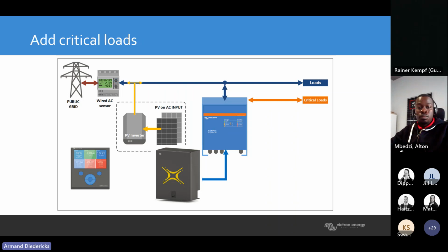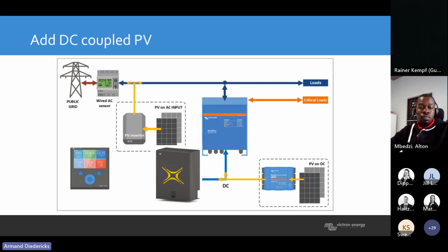and the PV inverter will switch off. If you want to add on additional PV modules on an AC coupled system, then you can add on MPPT. The MPPT's primary function is to charge the battery at first priority, and then, if the battery is full, it will provide power to the load. But if the load is higher than the MPPT's capacity, then obviously it'll start draining the battery.